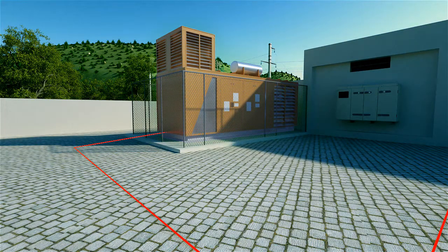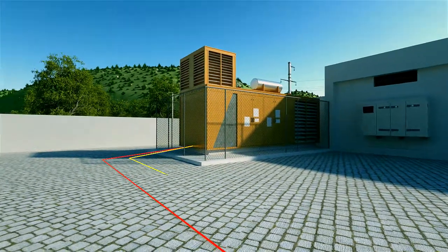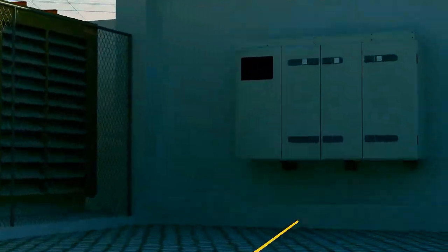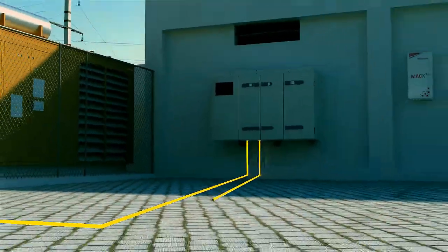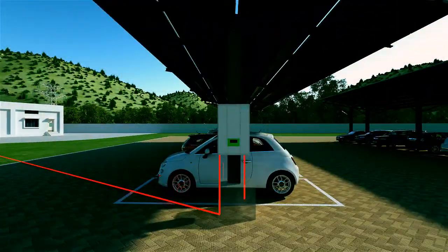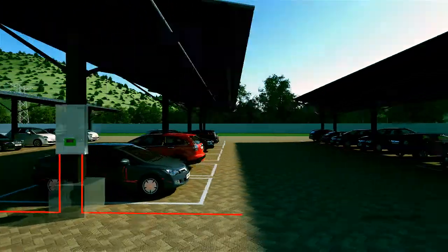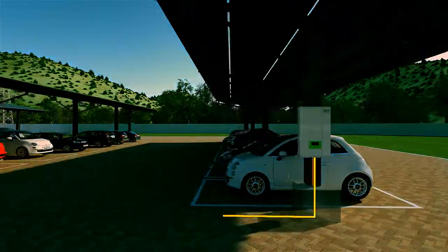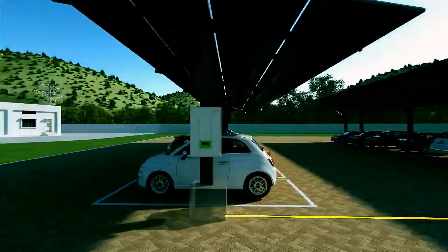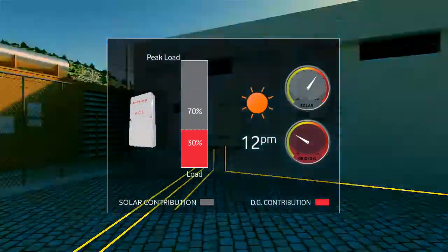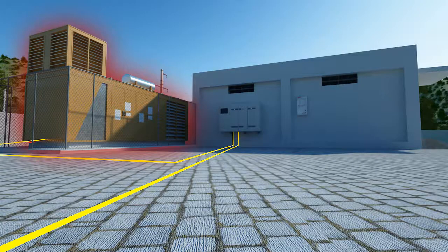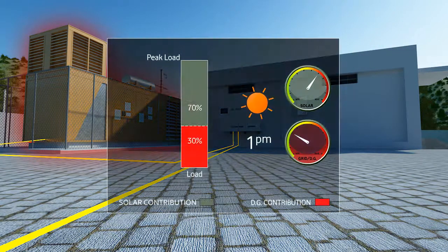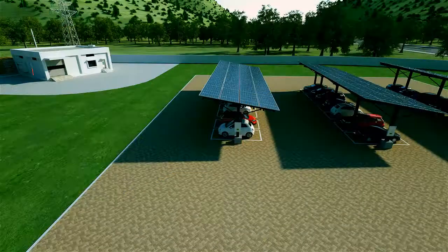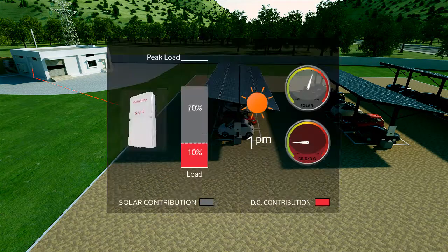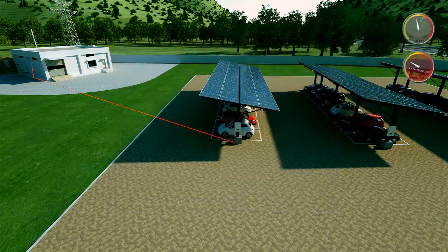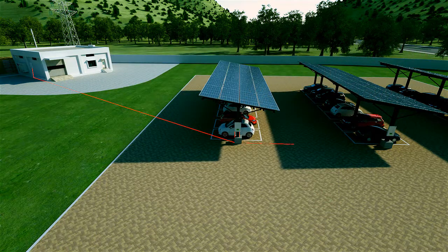The diesel generator will now act as a wheeling source and all the power to the plant will be fed by the diesel generator. MAX then sequentially powers up solar inverters, to ensure a smooth integration of solar power, and power drawn from the generator is reduced to 30%. If there is a sudden drop in load demand, MAX reduces solar power coming from inverters, ensuring that the diesel generator is operating at its optimal capacity and fuel efficiency.